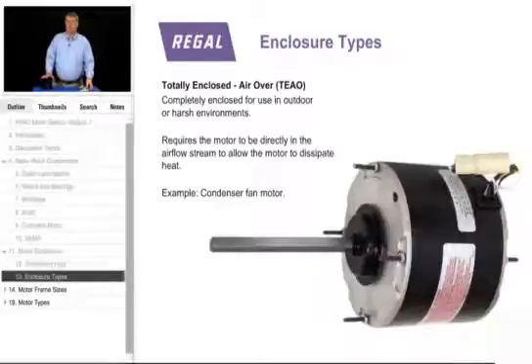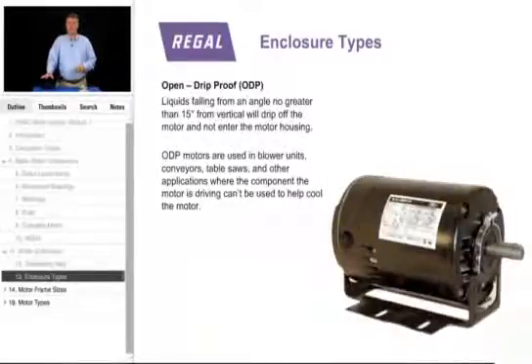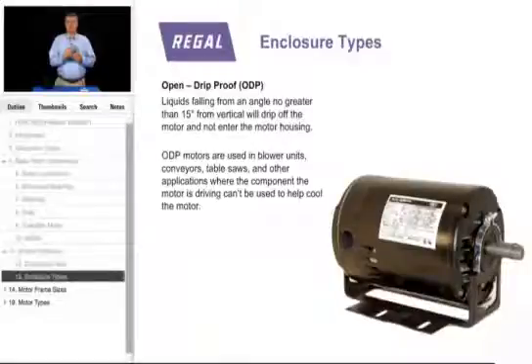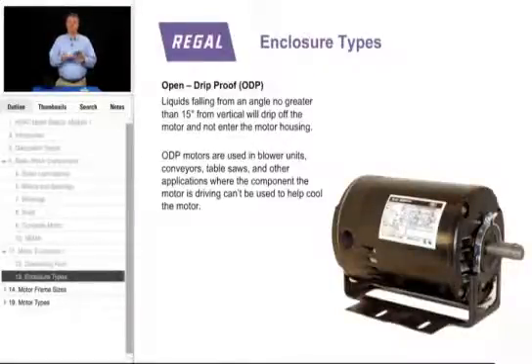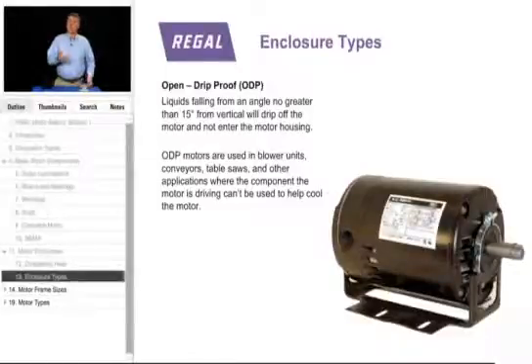The next type of motor is an open drip proof, or ODP. The NEMA nomenclature states that the motor must be enclosed 0 to 15 degrees on the shell and end frames to theoretically allow any light moisture, dust or dirt to drip off the motor without getting inside of it. The holes in the shell also help it dissipate heat.